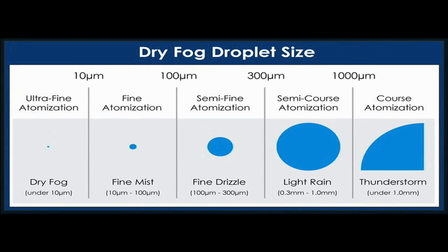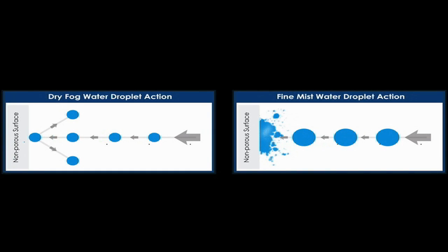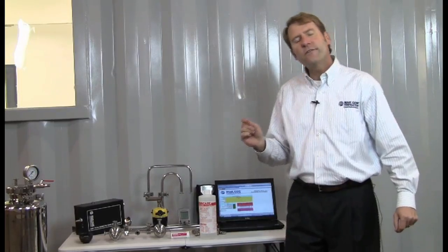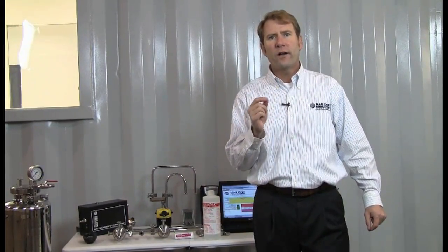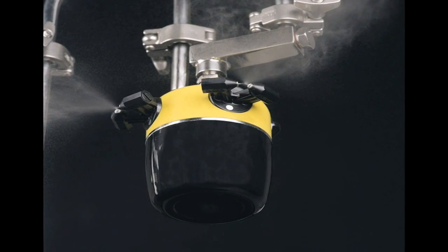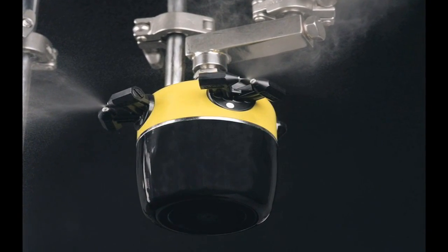The MAR COR Dry Fog System puts out a 7.5 micron droplet. That droplet is so small it does not wet down surfaces. It bounces off, it evaporates, and it does a vapor phase disinfection, leaving behind no residuals on any surfaces at all. You control the relative humidity in the clean room to ensure that the dry fog has gone everywhere, ensuring a complete and total disinfection.